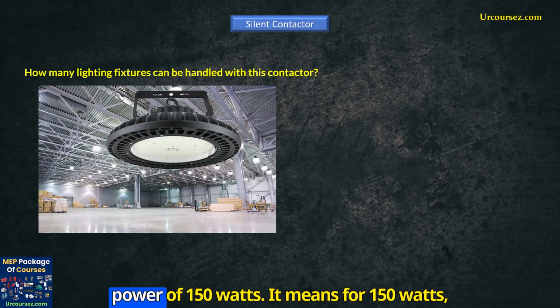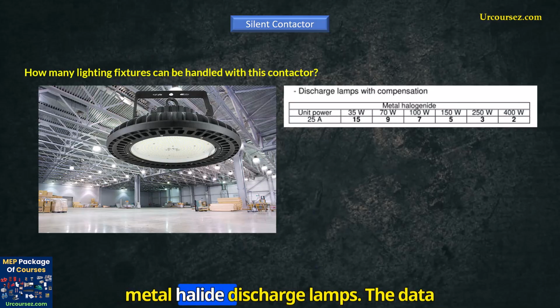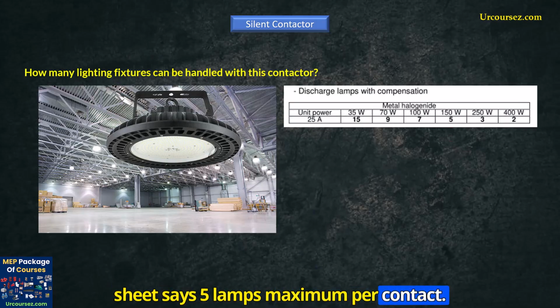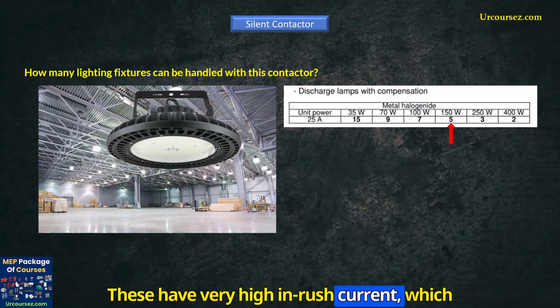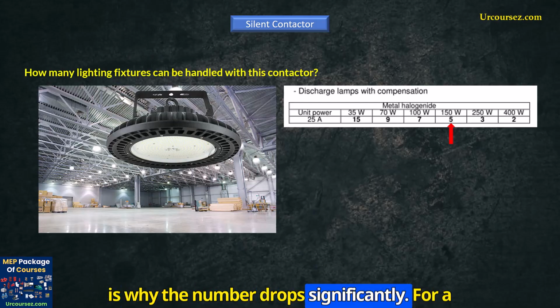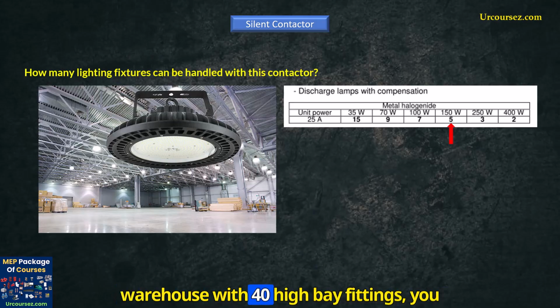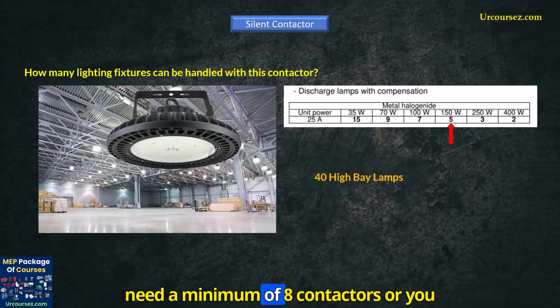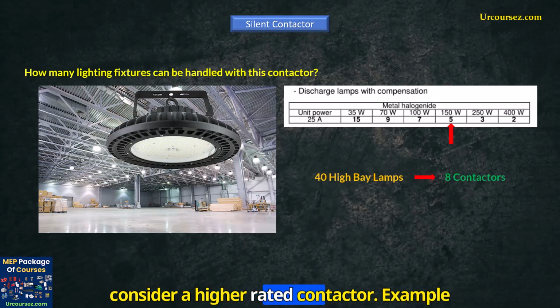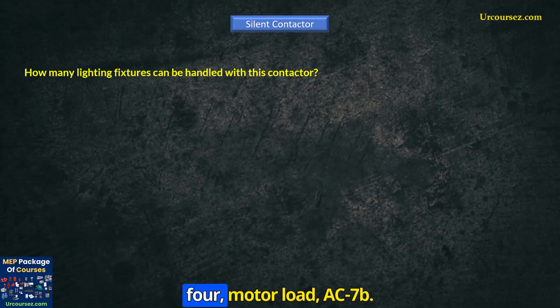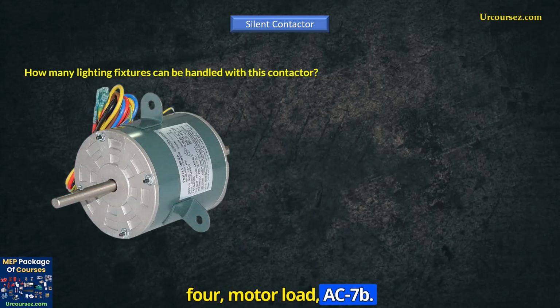Example 3, metal halide lamps or high bay lighting with a power of 150 watts. It means for 150 watts, metal halide discharge lamps. The datasheet says 5 lamps maximum per contact. These have very high inrush current, which is why the number drops significantly. For a warehouse with 40 high bay fittings, you need a minimum of 8 contactors or you consider a higher rated contactor. Example 4, motor load, AC7B.